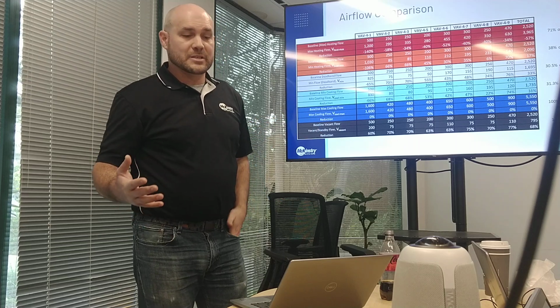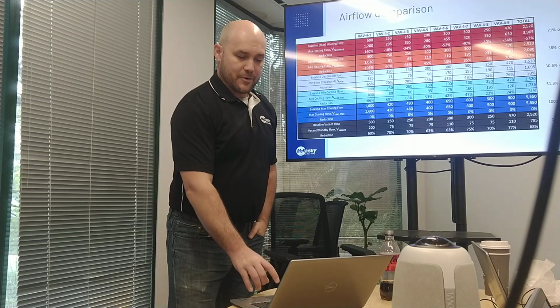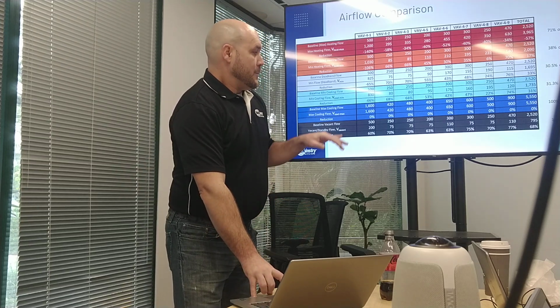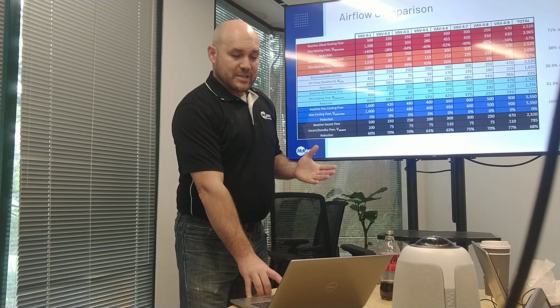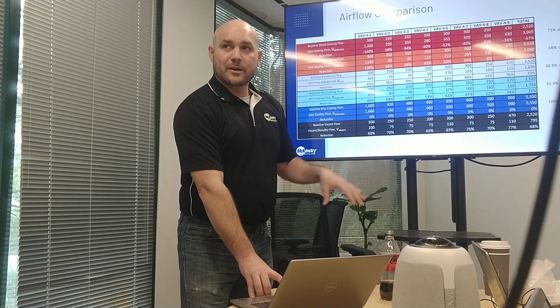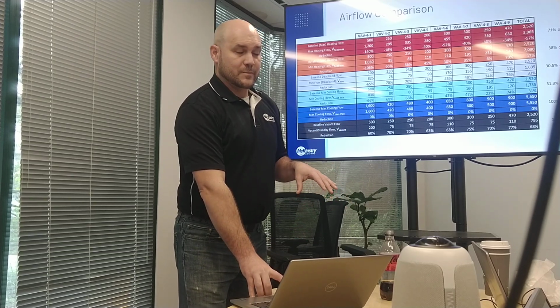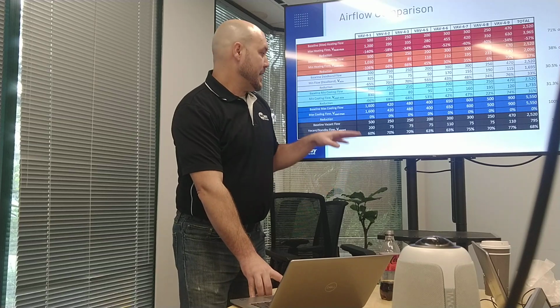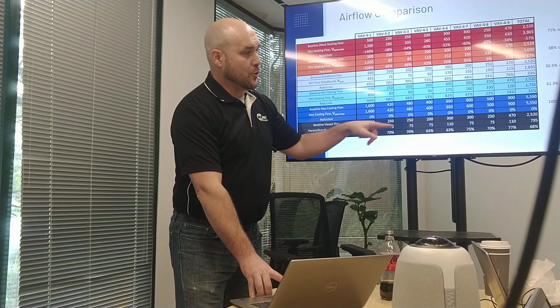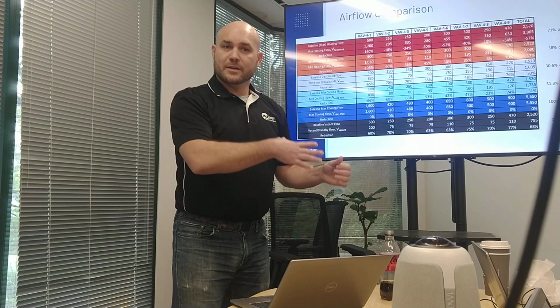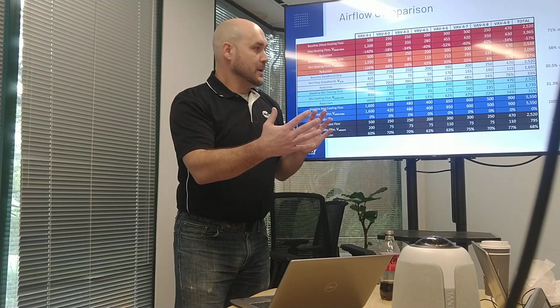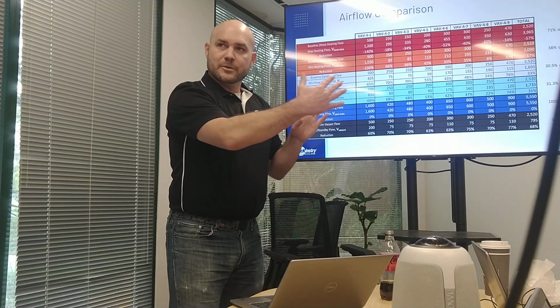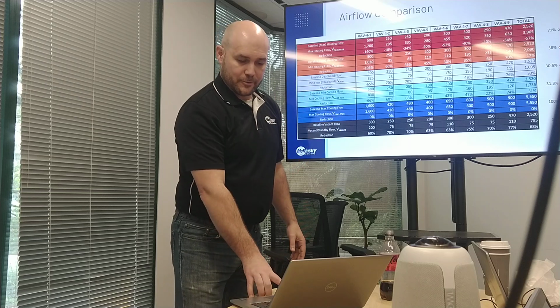So do they have an occupancy sensor? Do they have CO2 for demand control ventilation? Being able to determine if a space is vacant, and therefore being able to drop out that minimum, the people component of ventilation, allows you to operate in this regime a whole lot more. And that, going back to the first graphic, allows the peak of that chart to move lower and lower, further to the left.